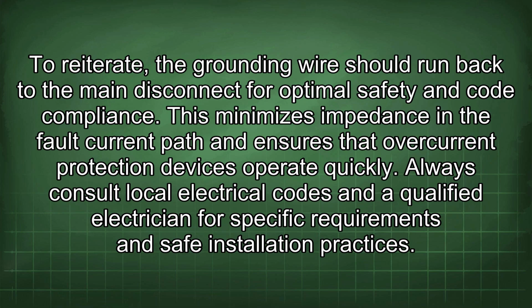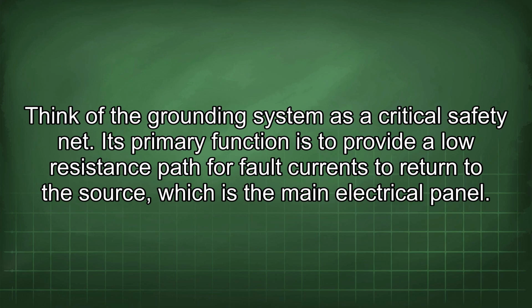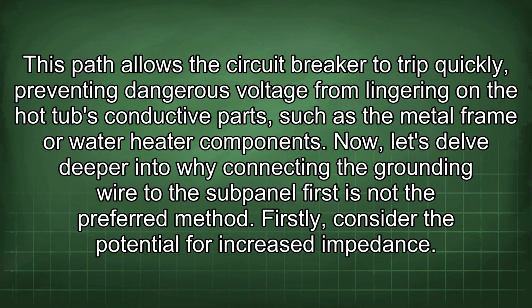To reiterate, the grounding wire should run back to the main disconnect for optimal safety and code compliance. This minimizes impedance in the fault current path and ensures that overcurrent protection devices operate quickly. Always consult local electrical codes and a qualified electrician for specific requirements and safe installation practices. Think of the grounding system as a critical safety net. Its primary function is to provide a low resistance path for fault currents to return to the source, which is the main electrical panel. This path allows the circuit breaker to trip quickly, preventing dangerous voltage from lingering on the hot tub's conductive parts, such as the metal frame or water heater components.